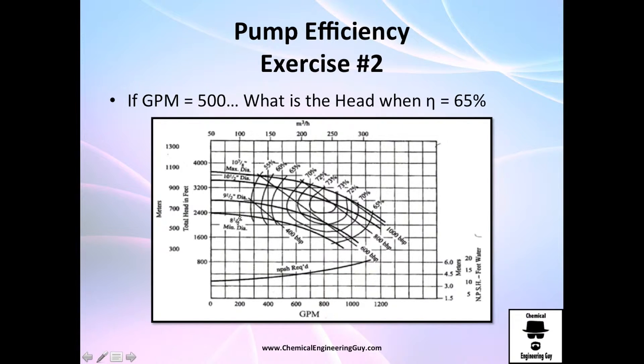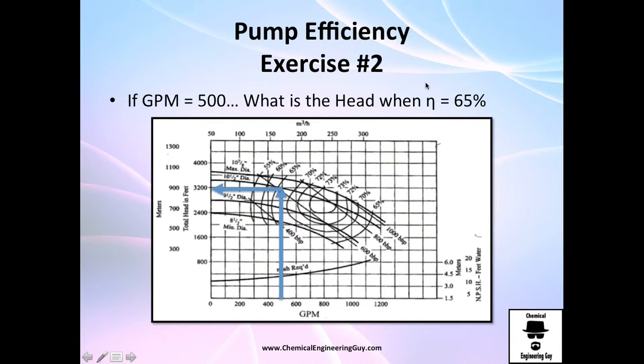Now we can get even more data. For example, if I tell you I operate a 500 gallon per minute process, what will be the head? If my actual operation is about 65% pump efficiency, let me find that pump efficiency line right here — 65%, this line.